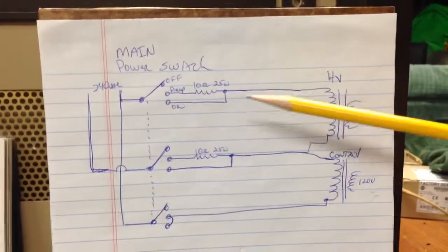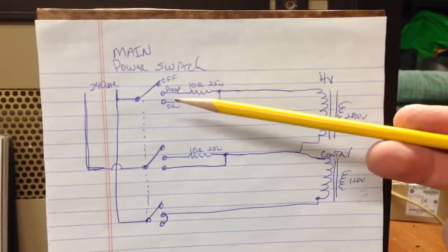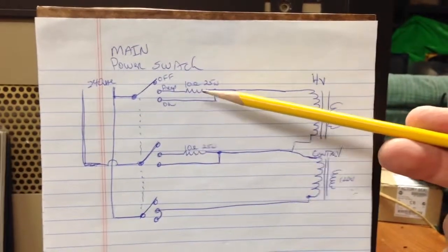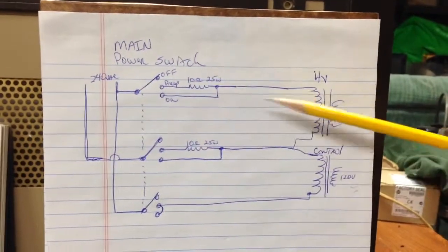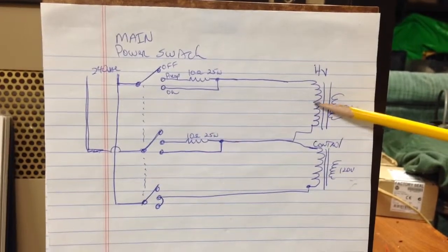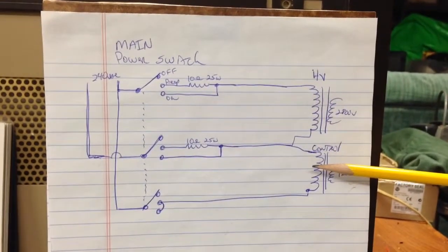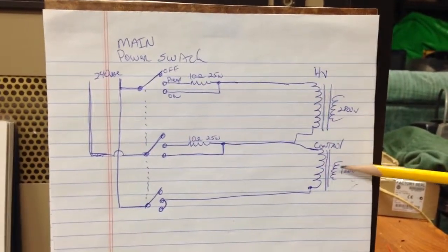What I'm going to do with it. So you'll have the off position and you'll have the prep position which you'll shunt with two 10 ohm 25 watt resistors. And that accomplishes your step start for your high voltage as well as the step on the control transformer.